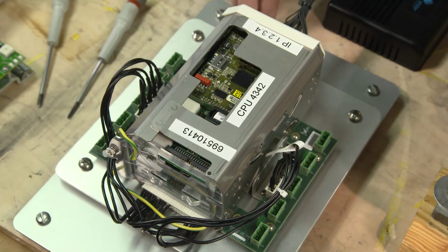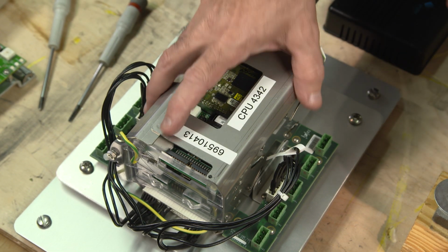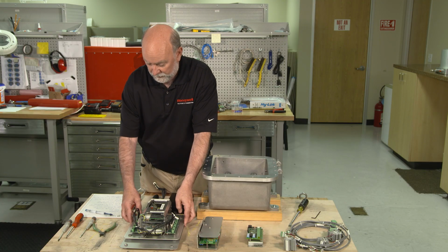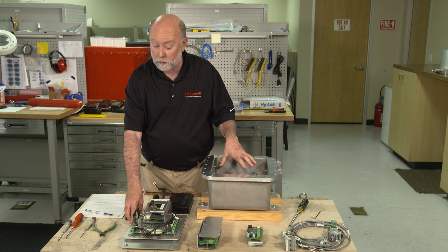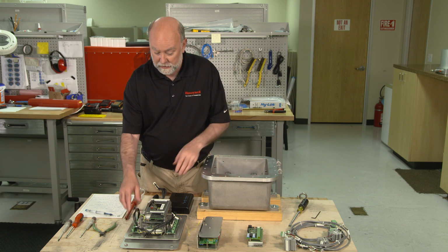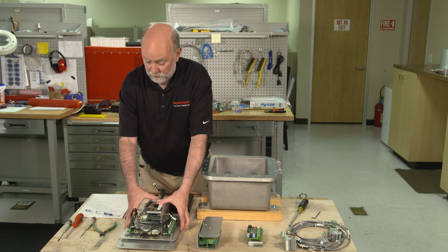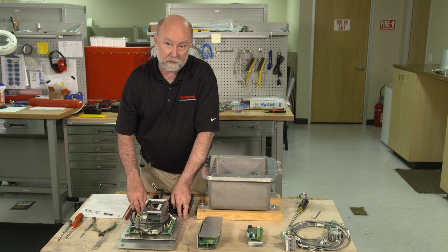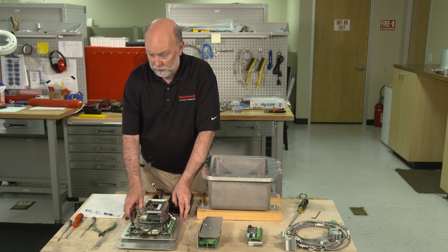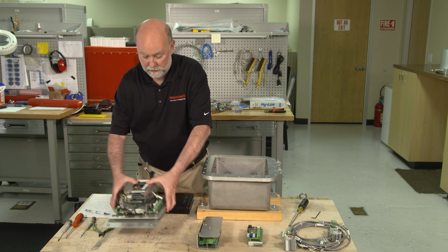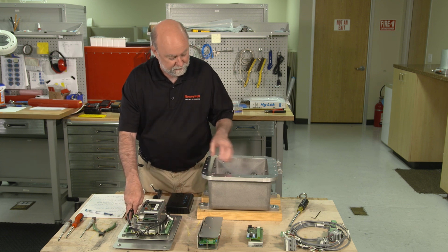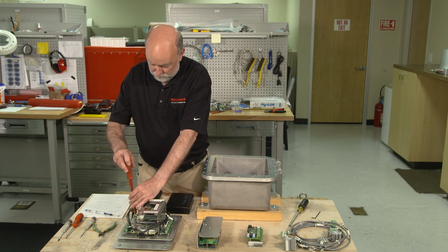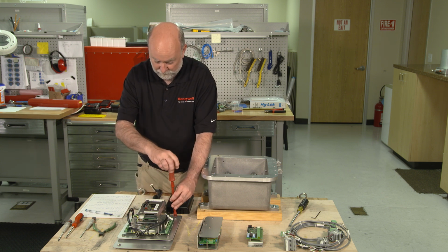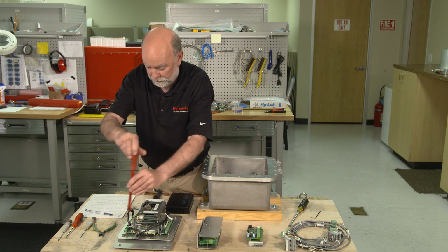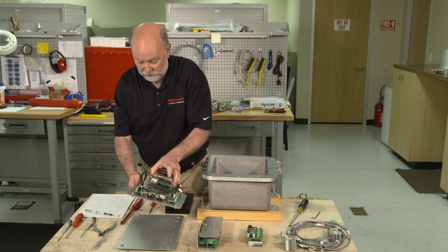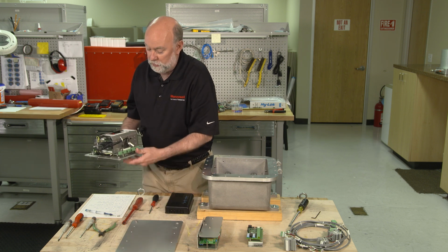Now, the new electronics module, the card cage here with the cards pre-installed on it, transducer adapter boards and so forth, is mounted on a square plate, which is designed to fit this Q.sonic 3 box. If we have the Q.sonic 5 meter, which has the larger rectangular box, the square plate is installed on the rectangular plate as it arrives to you. If you're going to install this plate into the larger box, you would put the entire assembly in there. To mount just the top plate into the smaller square box, we're going to unscrew this plate, which I've already pre-loosened these, from the larger plate to separate those. So that I can, if I don't need the larger plate for the Q5 box, I can set that aside or discard that.